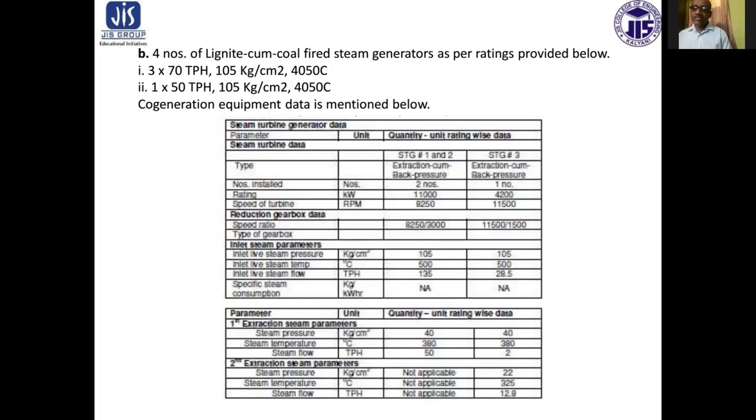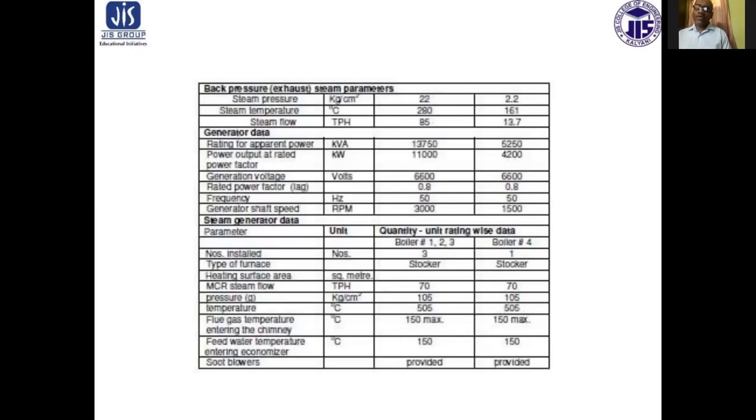The first extraction steam parameters: steam pressure 40 kg per centimeter square, temperature 380 degree centigrade, steam flow rate 50 ton per hour and 2 ton per hour. For the second extraction steam parameters: steam pressure 22 kg per centimeter square, steam temperature 325 degree centigrade, and steam flow 12.9 TPH.